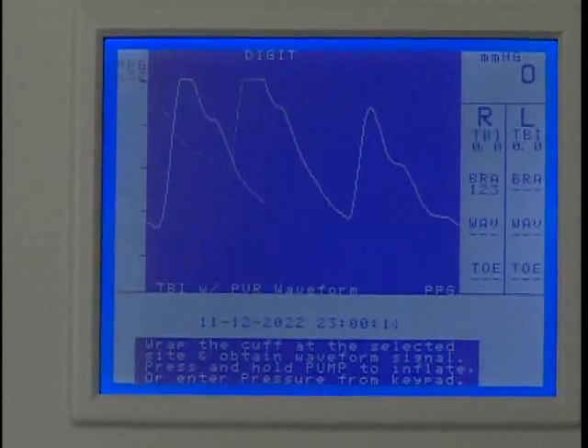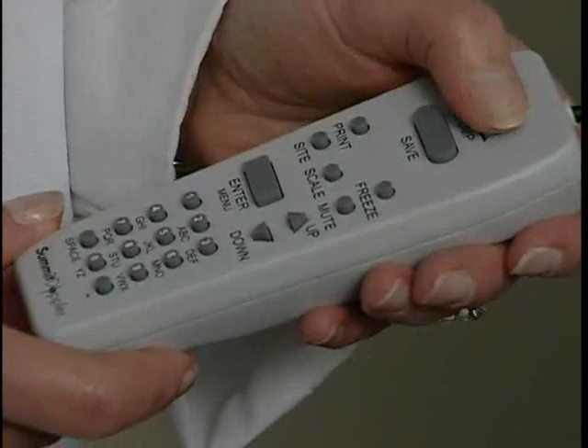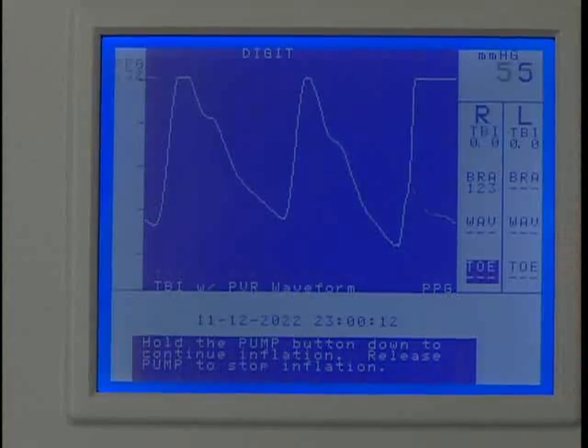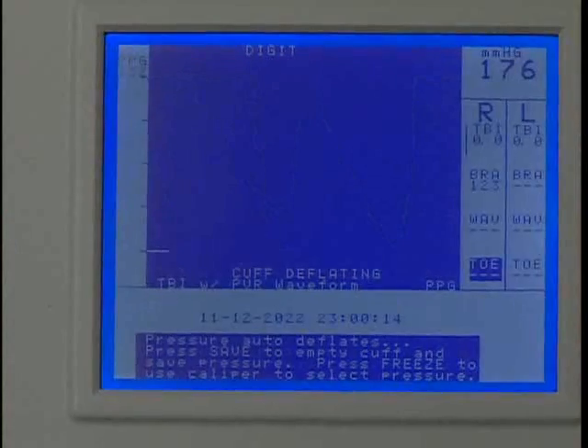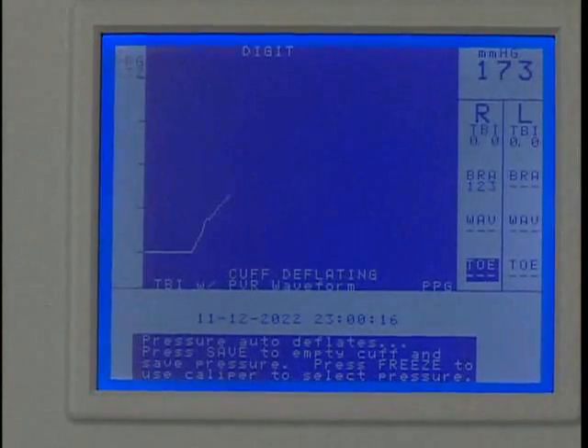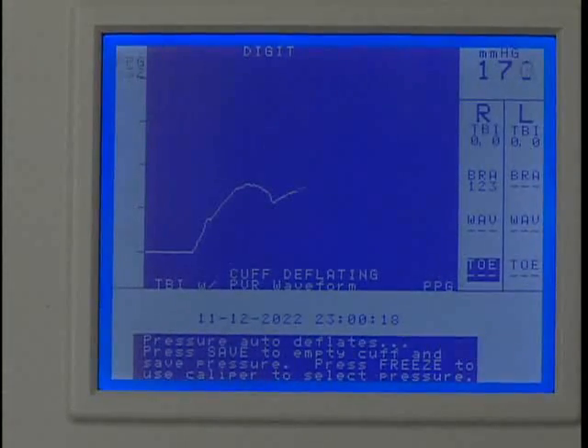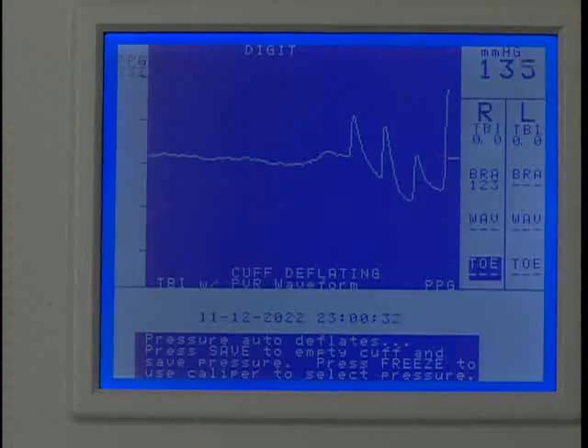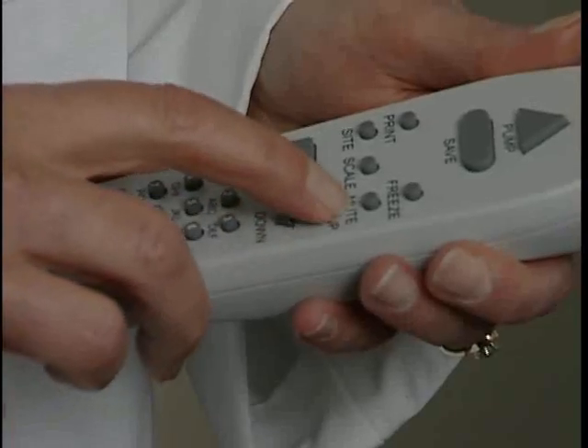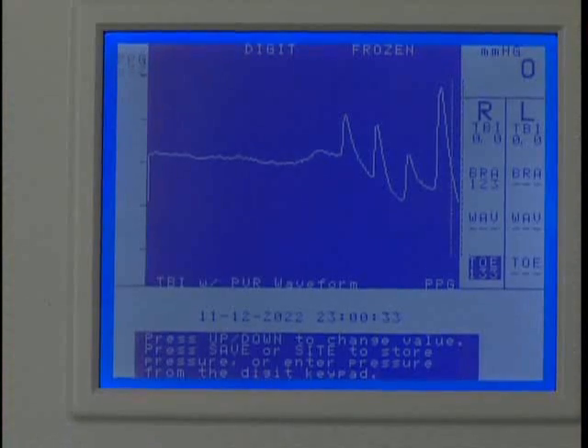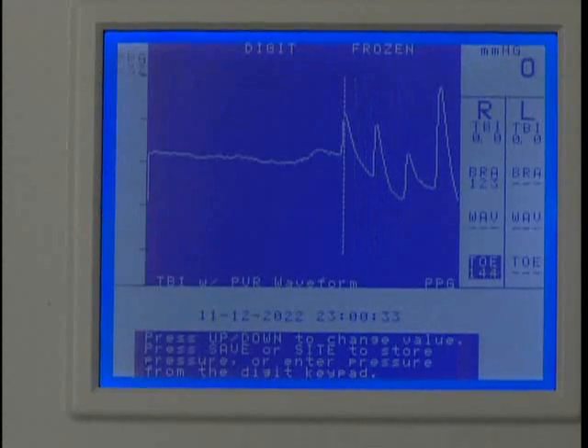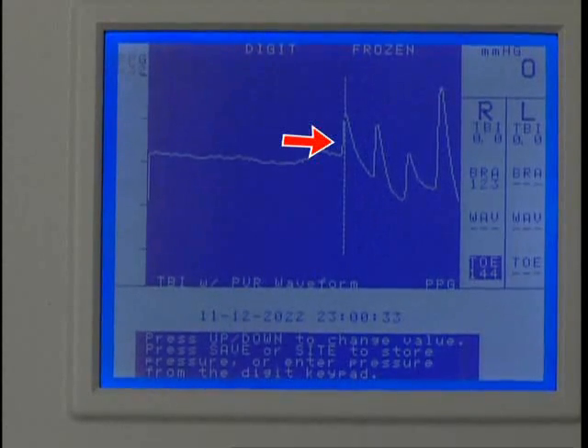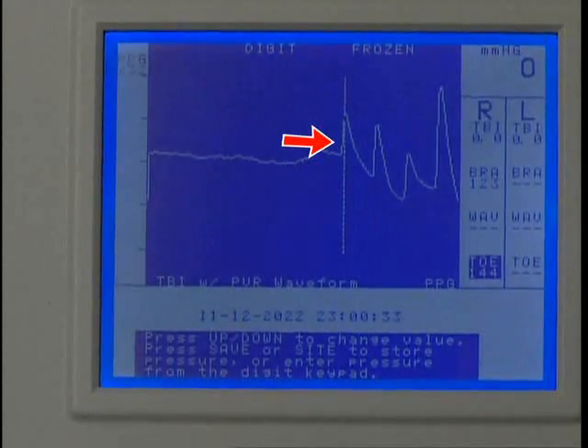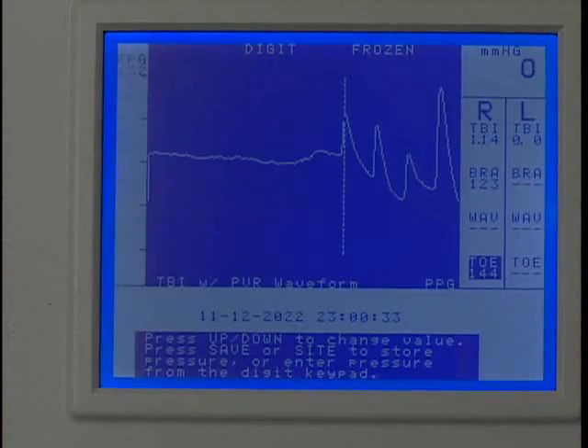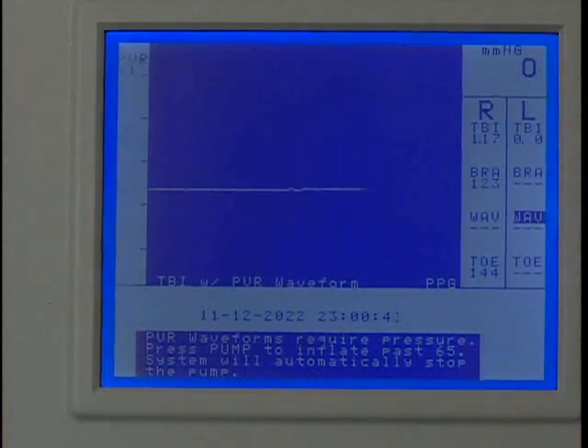Once an optimum waveform is viewable on the screen, press and hold Pump until the PPG pulsations disappear. Release the pump and the cuff will automatically start to deflate. Press Freeze after several pulses have reappeared. Press the up or down key to move the caliper tool to the beginning of the first upward slope at the start of the pulsation, as shown. This is the systolic pressure. Press Save to record it, and the marker will move to the next protocol location.